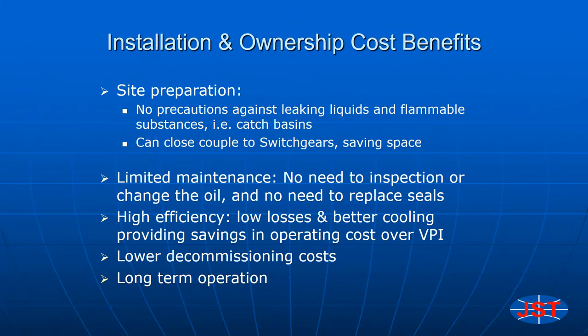While the purchase price of buying a better performing, highly reliable and environmentally safe transformer may be a bit more costly up front, these costs can be made up over the long run as a result of the installation and cost of ownership benefits associated with cast resin transformers. Site preparation is greatly simplified by negating the need for catch basins needed for liquid-filled transformers. You can also save on real estate by close coupling to switchgear. Maintenance is significantly reduced and is a matter of keeping the transformer clean. The lower losses when compared to other dry-type transformers help save on energy costs. Lastly, decommissioning costs are much less than liquid-filled with respect to waste disposal.